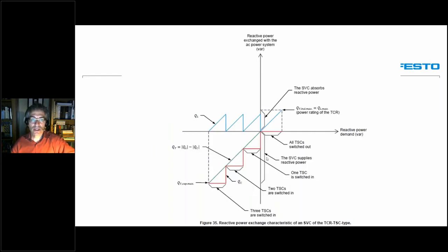So this will yield something like that. When the three capacitors are in the circuit, our inductor can change its value to compensate up to its maximum. Then we switch out the third bank of capacitors, leaving only two. We compensate from two to one, then switch out the second, leaving only one bank of capacitors, and compensate it. Finally, when no capacitors are in the circuit, we can absorb more reactive power with an inductor.